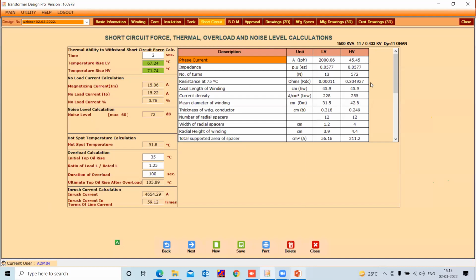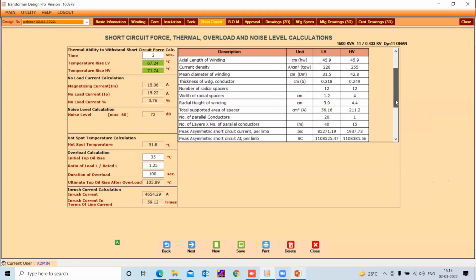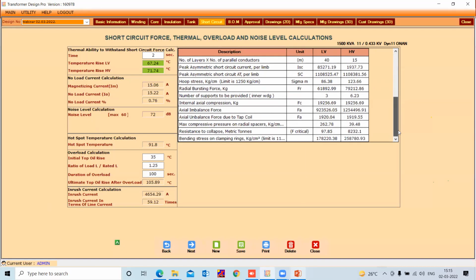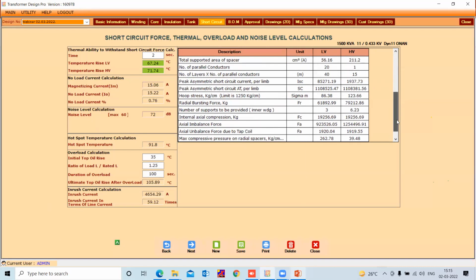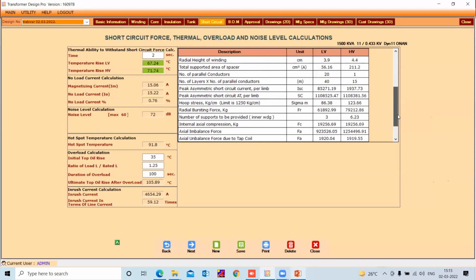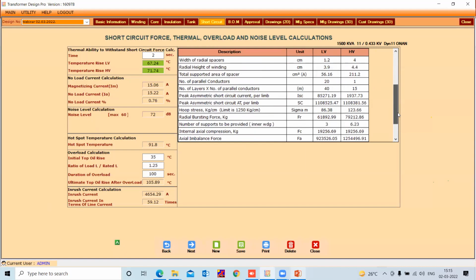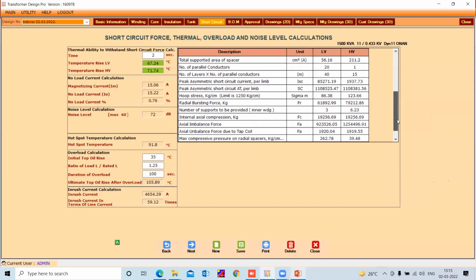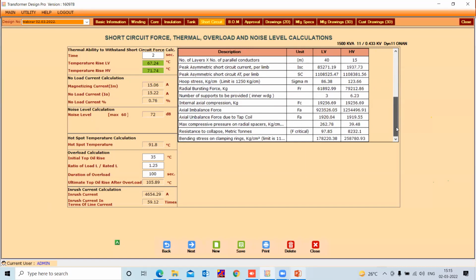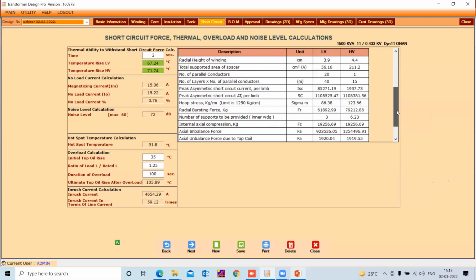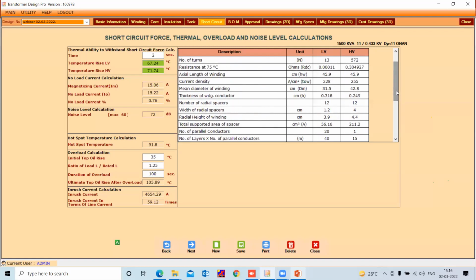Now you can see the right hand side table. The table is according to IEC formulas. In that you will get the number of axial conductors, the number of parallel conductors, and the hoop stress information, radial bursting force information, imbalance and balance forces for LV and HV coils, collapsing resistance, bending stress. So this much information as per IEC formulas you will get over here.